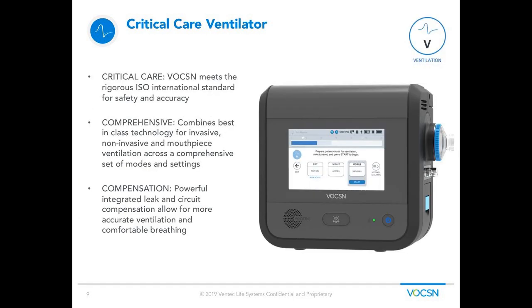So first and foremost, that critical care ventilator. Ultimately, VOCSN is a Class 2 critical care life support ventilator. When we say critical care, what does that mean? It means it meets a higher standard, an international standard for safety and accuracy. Every portable ventilator has to be safe and accurate within a certain spec, but the spec for VOCSN is much tighter. That means in temperature fluctuations or shock and vibration situations, if you think about a ventilator that's in an air-conditioned room and then goes out into the heat of the summer, or it's on the back of a wheelchair going over cracks on a sidewalk with that shock and vibe, other portable ventilators are going to struggle to maintain that safe and accurate window. VOCSN is going to maintain very comfortable ventilation for the patient. The patient actually feels those adjustments during shock, vibration, and temperature fluctuation situations. VOCSN maintains safe and accurate ventilation across all of those different environments.